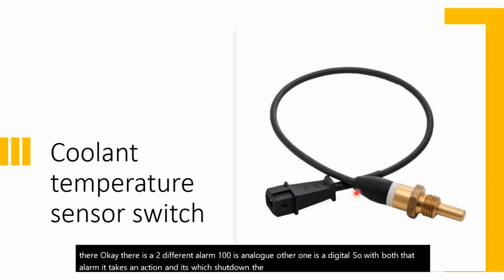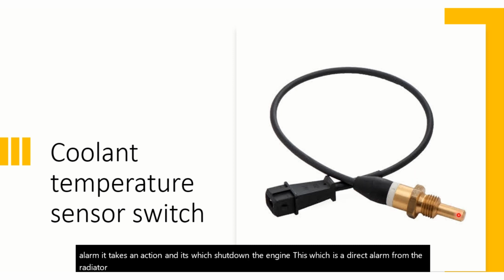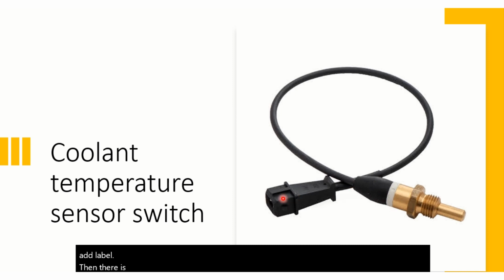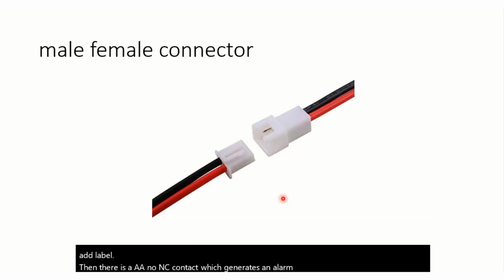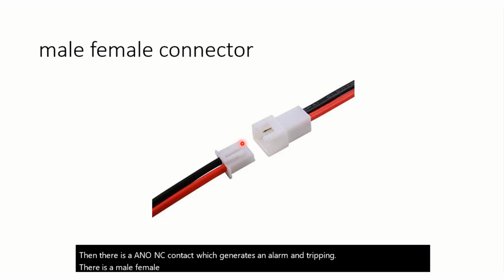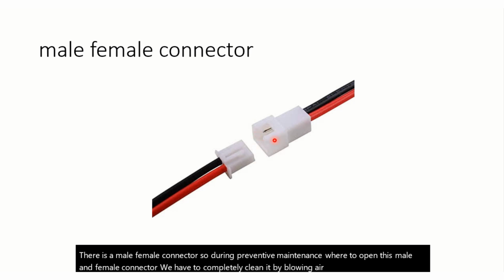This switch is a direct alarm from the radiator. It directly monitors the temperature of the coolant, and once the temperature increases up to a level, there is a NO/NC contact which generates an alarm and tripping. There is a male-female connector. During preventive maintenance, we have to open this male and female connector, completely clean it by blowing air inside, and refit it properly.